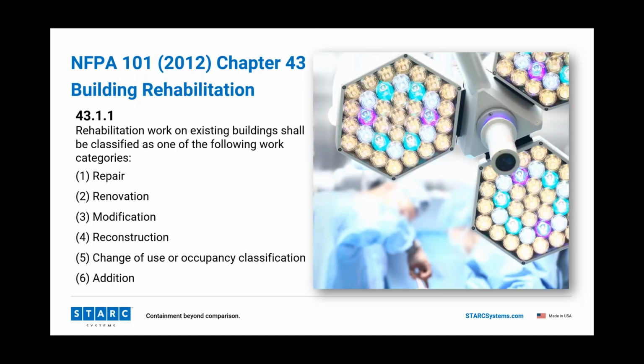Let's look real quickly at the Chapter 43 rehabilitation. There are hour-long presentations on Chapter 43 alone. There's a great one out there by Jim Peterkin. I recommend you go look it up. There are six different classifications of building rehabilitation. We're not going to get into each one of them, but I do want to point out that these have implications. Chapter 43 tells you when you have to meet any of the new chapters, so Chapter 18 for healthcare, right? It tells you if you have to bring an existing building or an existing system up to the new occupancy requirements, or if you are permitted to remain with the existing occupancy requirements.